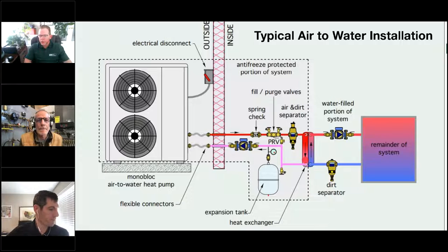If you had no buffer tank, you could glycol charge the whole thing and have no heat exchanger. The whole thing. Yeah. And that's a good point too, because when I worked in Colorado, in a scenario like this, it depends on how cold it is where you live, but maybe you have 40% glycol on the left side and you have 20 on the other. I mean, below 20 people weren't crazy about either, but in this scenario, we're showing water filled on the right and then glycol on the left.